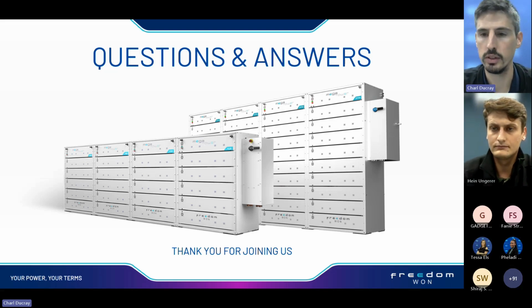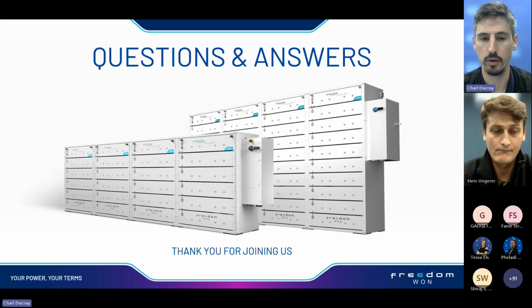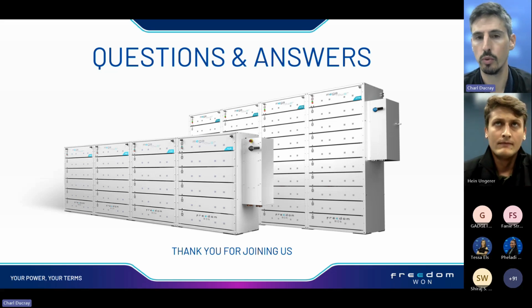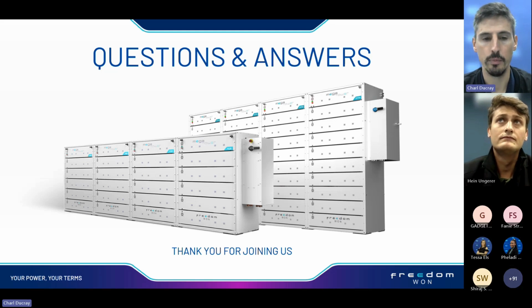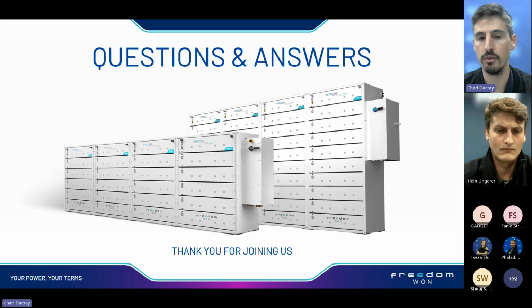So just in terms of the warranty, maybe it's a good chance to give a bit more information on that. As we have done with the light battery range, we've done the same with the megaTower range, where we now support a standard warranty and an alternate warranty. The standard warranty, which supports 8,000 cycles, requires a slightly lower C rating than your alternate warranty, whereby we support 0.5 C on your discharge and 0.25 C on your recharge. With the alternate warranty, whatever the maximum possible power output of that particular battery is will be allowed. However, in that scenario, cycles will be limited to 6,000 warranty cycles.